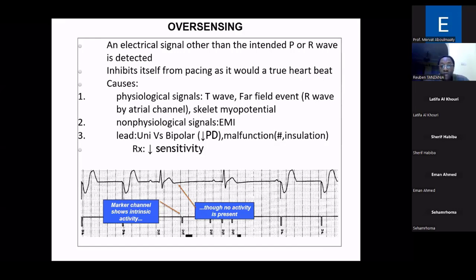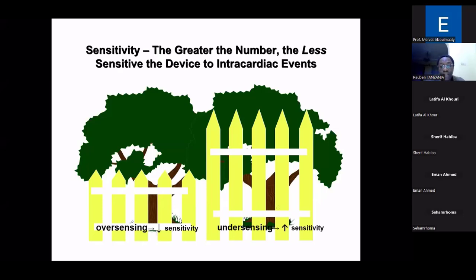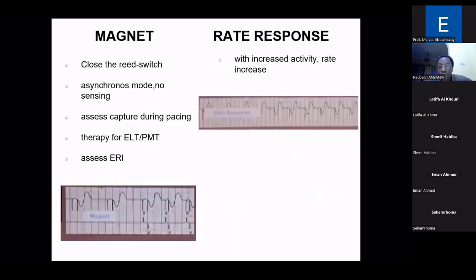Oversensing: here an electrical signal other than the intended P or R wave is detected, and the pacemaker inhibits itself from pacing as it would with a true beat. The causes are many, including physiological signals like the T wave or far field events, skeletal muscle potentials, but also non-physiological signals like EMI, and also lead associated causes. You have unipolar versus bipolar, but also malfunction of the lead, including lead fracture and insulation problem. The treatment of oversensing is to reduce the sensitivity. And these are examples of oversensing and undersensing. In oversensing, you are seeing too much, while in undersensing, you are seeing too little. So for oversensing, you have to reduce the sensitivity, and for undersensing, you have to increase it.